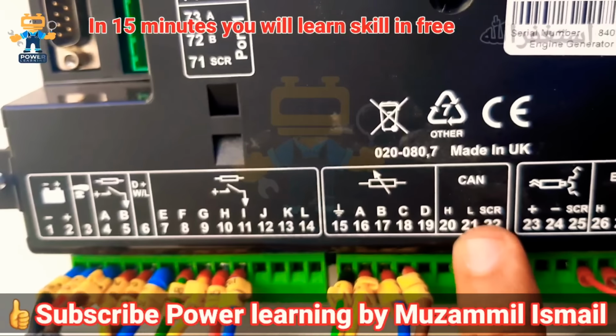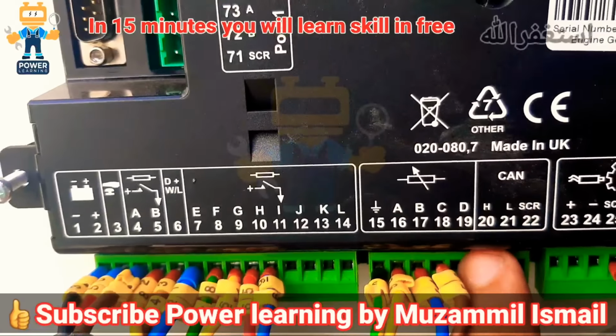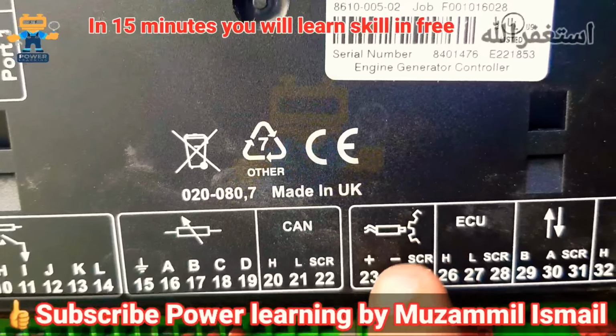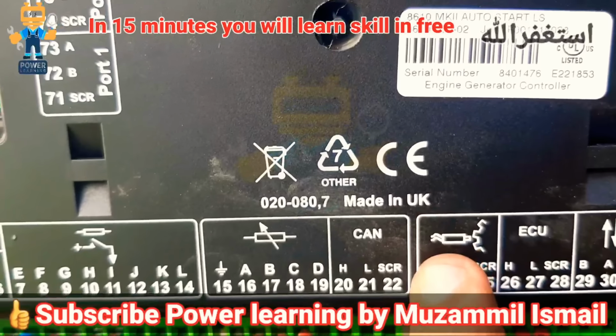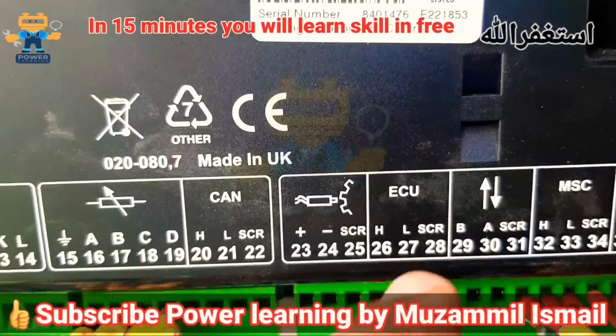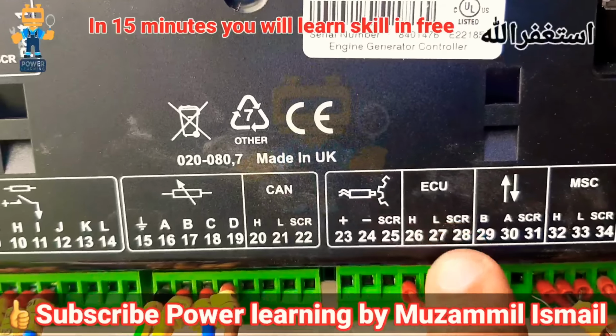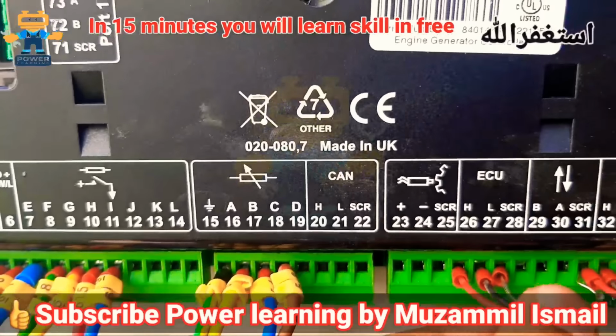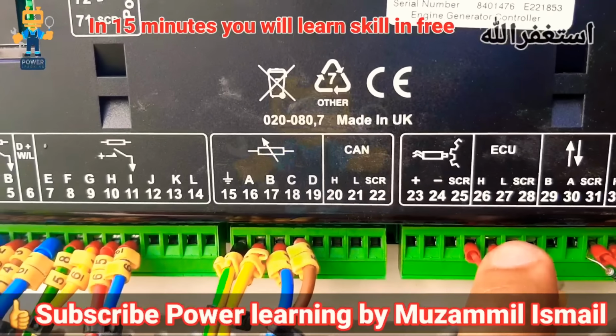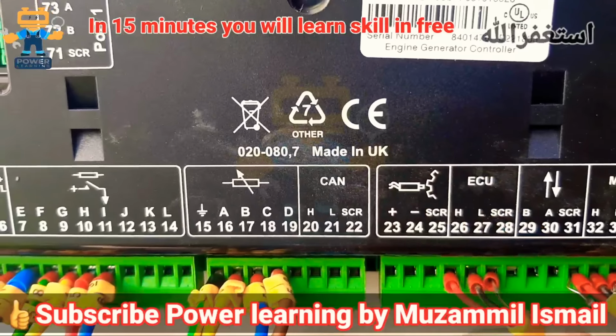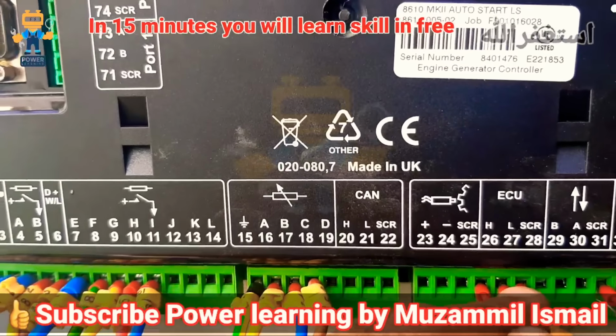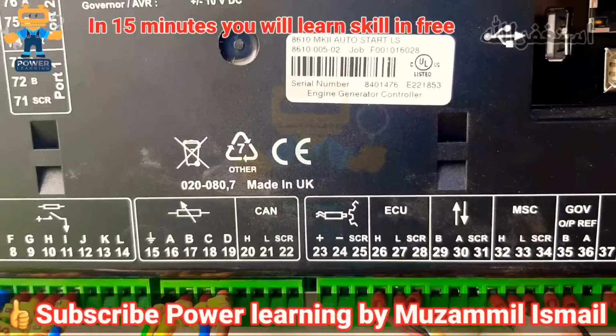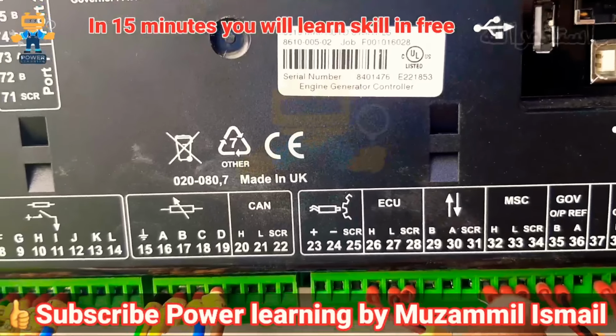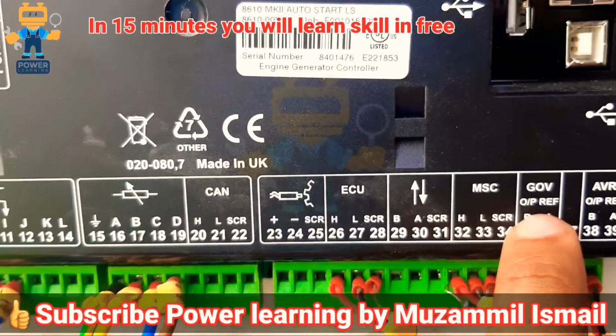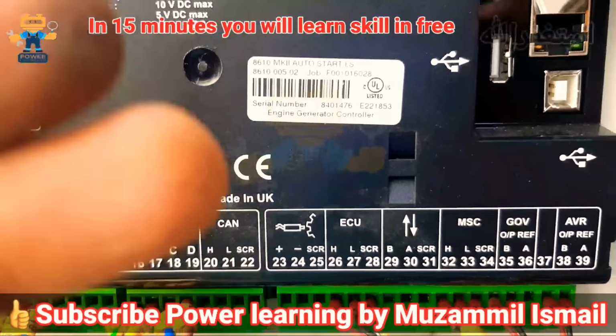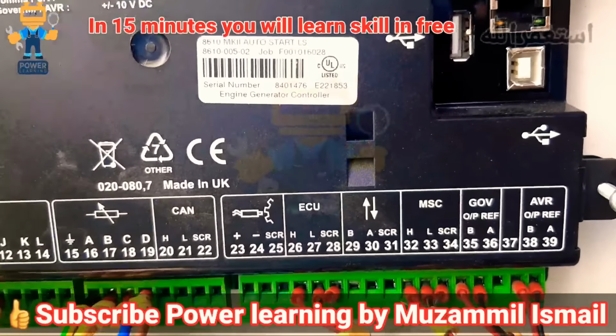After that this is CAN bus, optional CAN bus, which we are not using in this engine. This symbol is showing MPU, magnetic pickup unit. Because this is an electronic engine, we are not using MPU here. But after that here we have ECU. This is an electronic engine, so we have ECU. This is an engine with ECU. So for ECU card communication we connected the CAN bus cable here. This is the CAN bus cable which is connected between the controller and our ECU. So all the data from the engine is collected via this data cable, and after that we see it on our controller. This is the MSC cable, multi-set controller. Between all 3 generators we connected this multi-set controller.